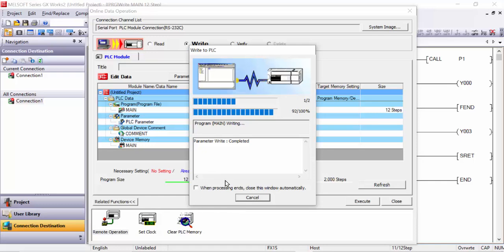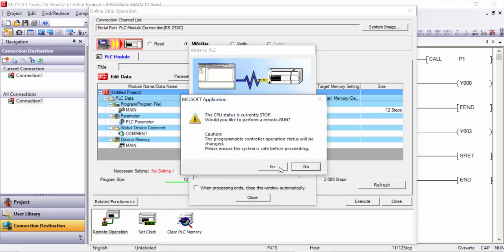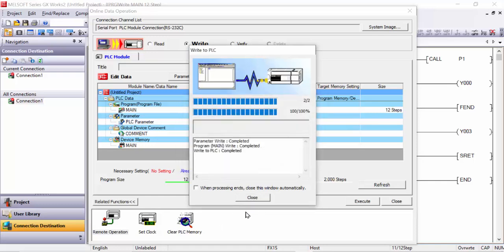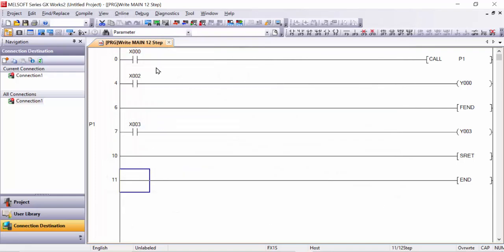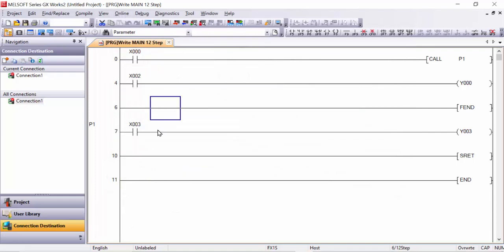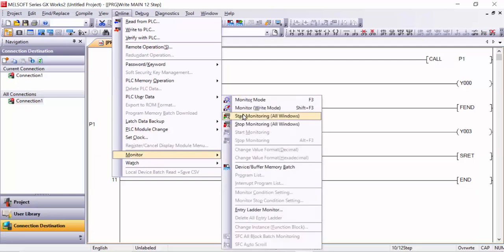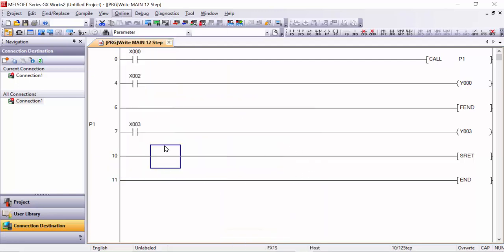In Mitsubishi PLC, you must stop the PLC first before writing the program; otherwise the program will not be written. Also note that compilation is manual here — it is not auto-compiled. After writing, go to Monitor and start monitoring.